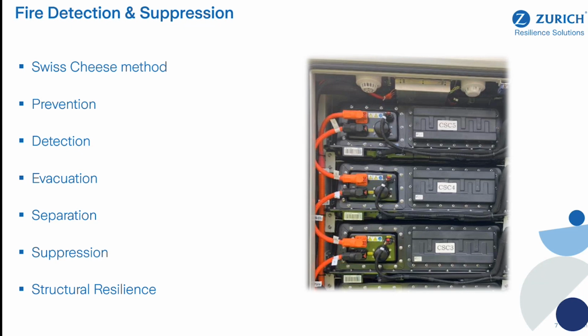And the analogy I would use there is kids' birthday cake candles. If you use the trick ones that reignite themselves, this could happen with a battery pack that's undergoing a thermal runaway event. So a one-shot suppression system might lead you into a false sense of security that you've quenched a fire. You may have quenched the fire, but maybe 5-10 minutes later, maybe even hours later, it may reignite itself. So yeah, it's useful, but not a magical solution to it. Structural resilience, again, like I mentioned earlier, fire-rated containers would help prevent the spread of fire. So I'll move on to the next slide.